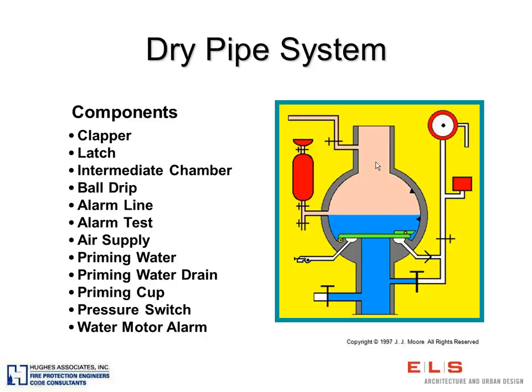And if a sprinkler breaks, pops off, you have a fire, any of those scenarios, most likely, of course, a fire incident, then the air that is under pressure will be released, and this valve will pop open, and then you will get water flowing out to your system.